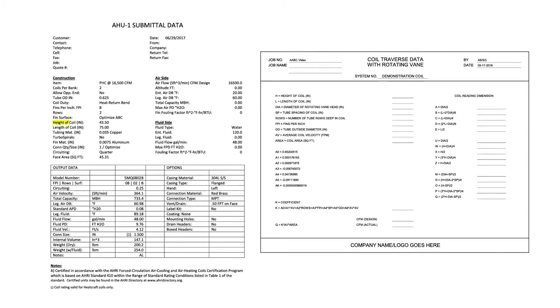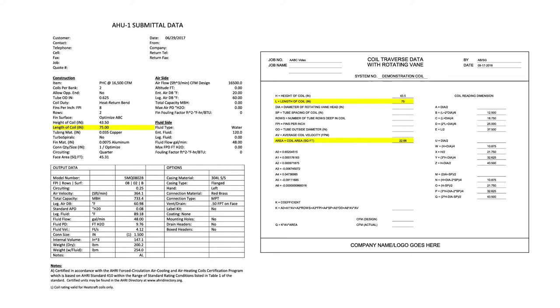From the submittal data, record the height of the coil: H equals height of coil as 43.5. Notice the coil reading dimensions are automatically calculating on the right of the form. From the submittal data, record the length of the coil: L equals length of coil as 75. Notice the coil area is automatically calculated as area equals coil area as 22.66 square feet.